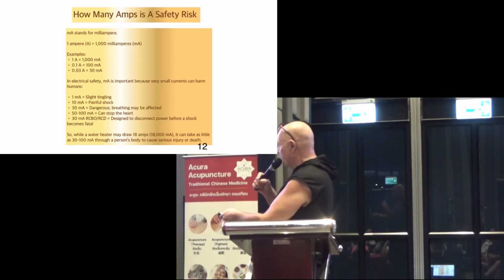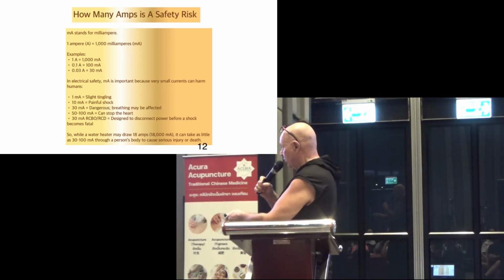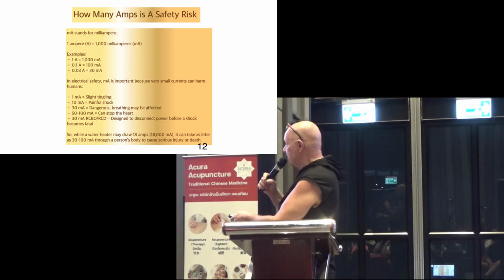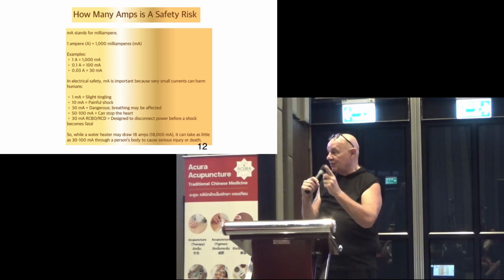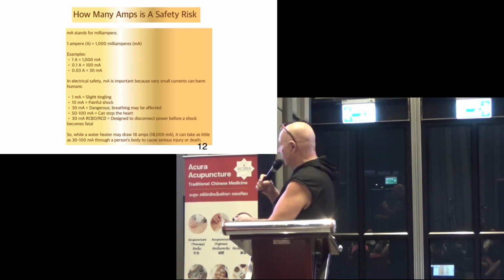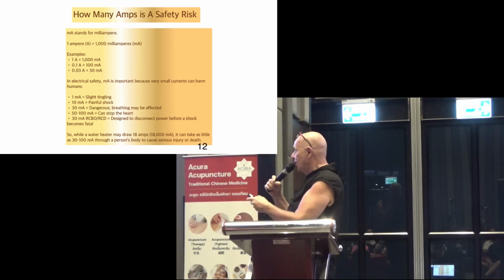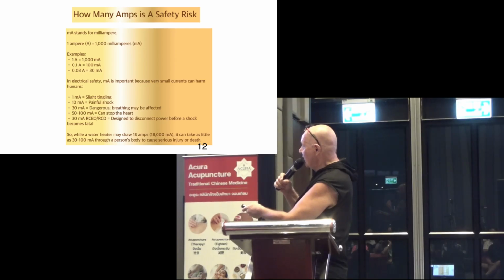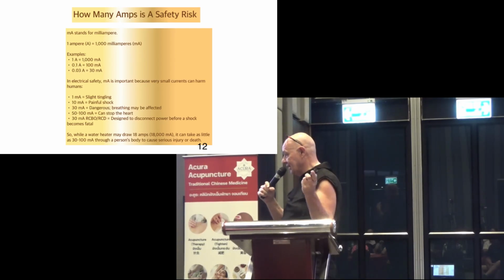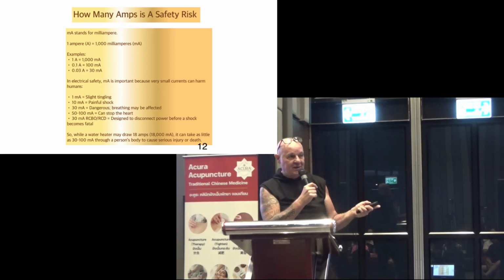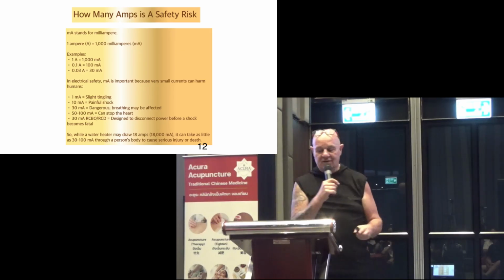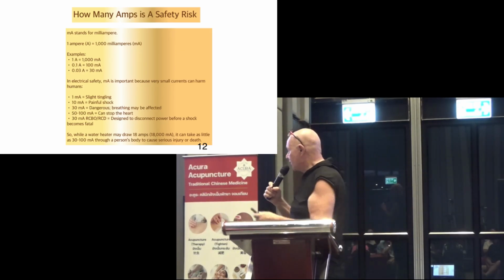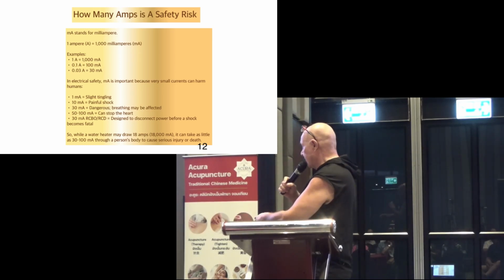Slight tingling sensation. 10 milliamps, you get a painful shock, probably the same as what you get from acupuncture. 30 milliamps is dangerous - 30 milliamps is 0.03. If you think back to the other slide, your light bulb was 0.09 of an amp, so it's becoming dangerous. From 50 to 100 milliamps, it can stop your heart. That's milliamps - 1 amp is 1,000. If you think back to the water heater, that heater requires 18 amps.